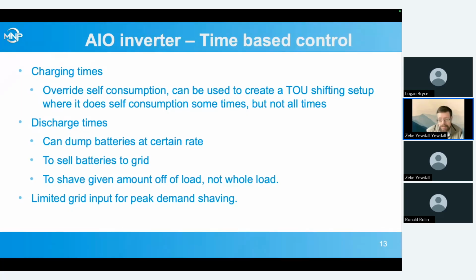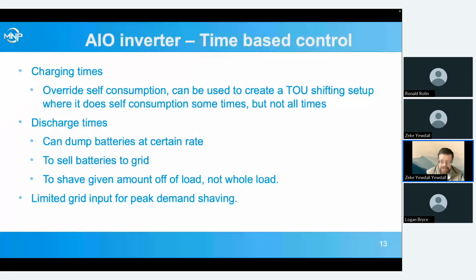There's some time of use setups where the utility has said, during this time period, here's your rate. And if you sell to the grid during that rate, if you buy, you get charged that much. And if you want to charge your batteries on off-peak later, fine with us. Most utilities haven't done that, but some of them said, don't care what you do with your batteries, here's the rates, and you can decide what to do. In that case, you might say, during this peak time, I just want to drain my batteries, selling it to the grid. If I've got loads at that same time, it'll go into that first, but any excess, I want to go to the grid because I'm getting paid this high amount for selling to the grid.